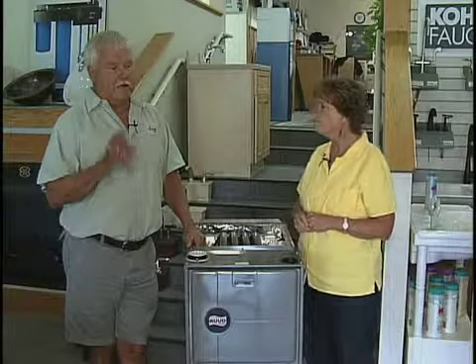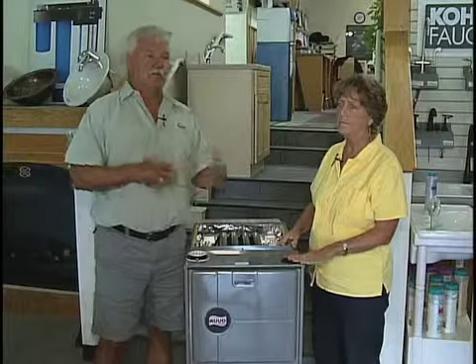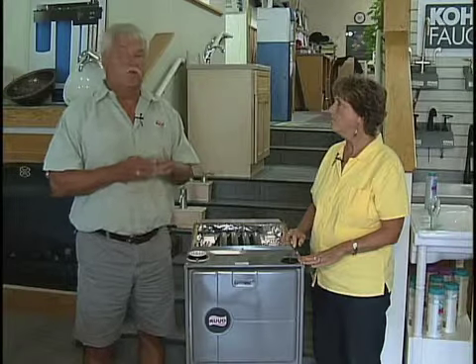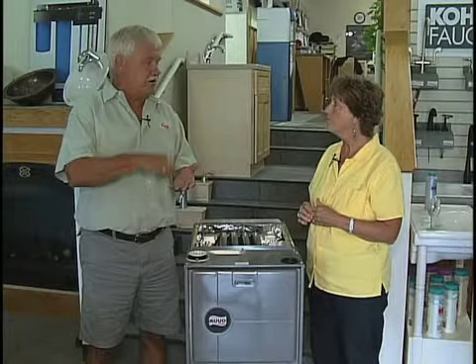Right, and that happens, Kathy, exactly what you say, when the furnace isn't running at its maximum capacity. And we size a furnace to heat your house when it's 30 or 40 below, but that hardly ever happens. So most of the time the furnace is oversized. And so it comes on and shuts off. Right, and so it's on for a pretty short period of time, and that's when you have that cooling effect.